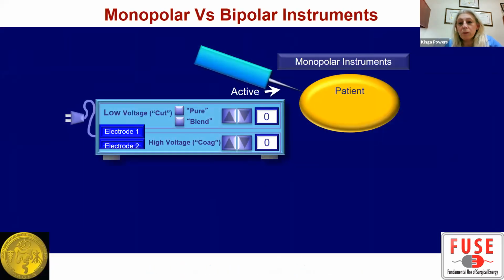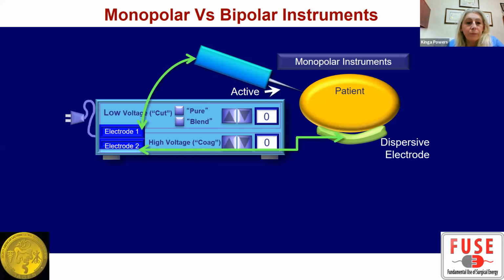In the monopolar mode, the instrument, like I showed before, the electrosurgical pencil or active electrode, the handheld pencil is here, the patient is this yellow blob, and the dispersive electrode is in green. So the current actually goes through the patient and disperses into the dispersive electrode.